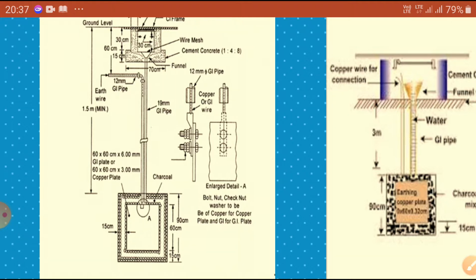The space around the earth plate is filled with alternate layers of charcoal and salt. The earth plate is connected to a 12 mm diameter pipe carrying the GI wire, and another 19 mm pipe is connected to the plate for carrying water from the funnel. A funnel with wire mesh is fitted at the top of the 19 mm pipe to pour water. At the top, cement concrete work is done to protect the system from mechanical damage.